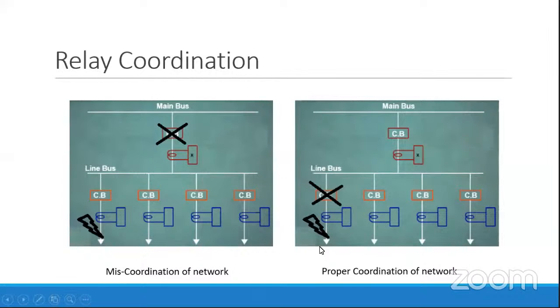the feeder, you can see the figure on the right hand side of your screen, that if there is a fault in feeder 1, the circuit breaker associated with this feeder only gets isolated. If somehow, due to some reason, this circuit breaker is unable to detect this fault condition, then and only then the incomer circuit breaker should operate, in order to prevent equipment on the incomer side from getting damaged, or the fault should not feed the upstream also.